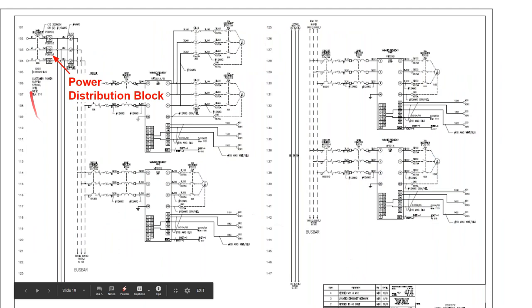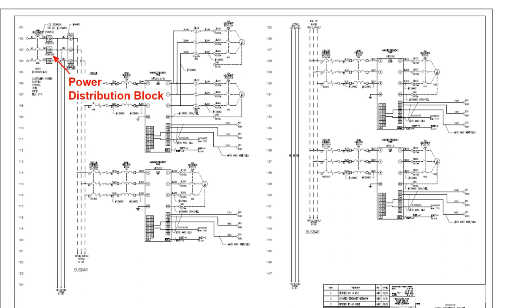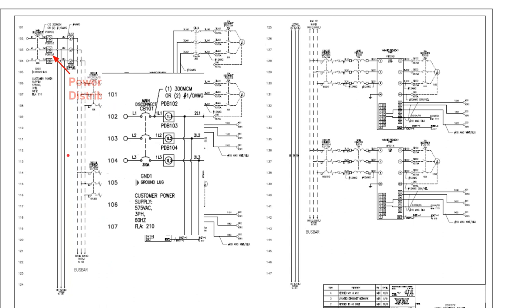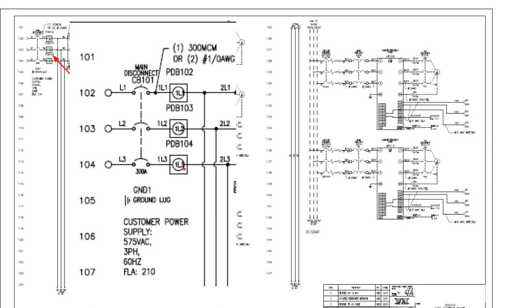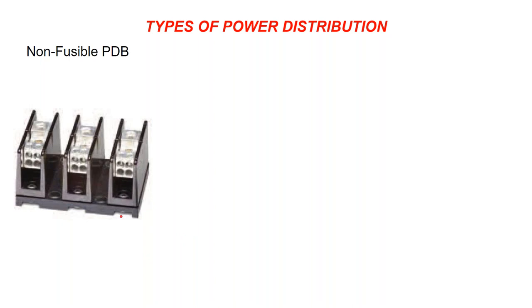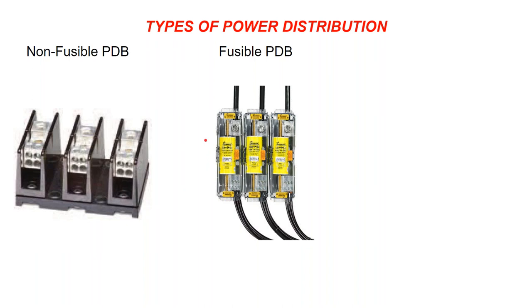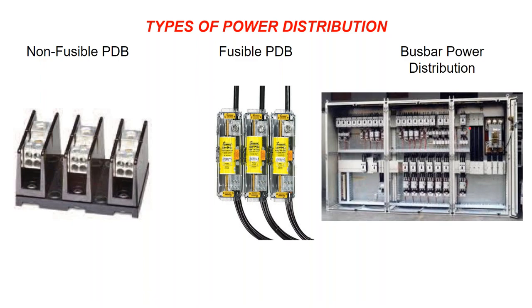After the disconnect, we have power and now need to distribute it using a power distribution block. Looking at the blown-up diagram, you can see the disconnect, the power distribution block, and different types of power distribution. Typically you'll see a block with a single conductor coming in and multiple conductors going out. Increasingly, fuses are being incorporated within the power distribution block itself to achieve the required short circuit current ratings.